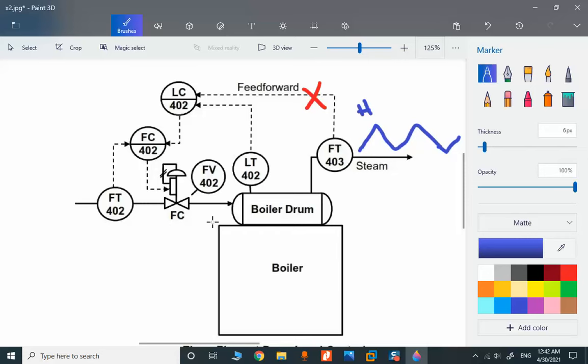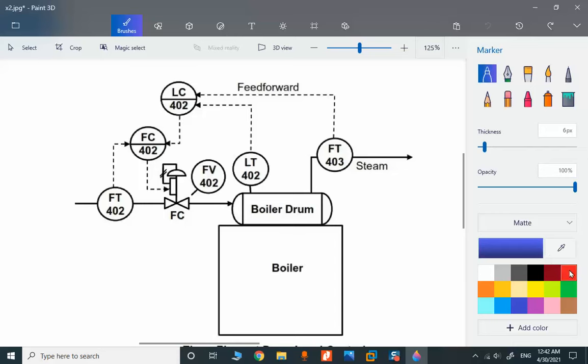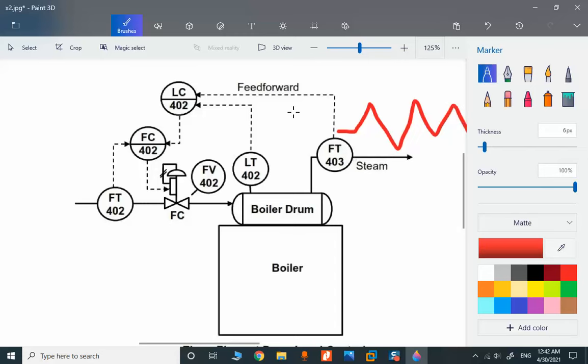We need to consider the steam flow as feedforward, as extra information. In this example, if steam flow is fluctuating, we want to use this feedforward to inform the master level control and by regulating the water flow, we compensate.